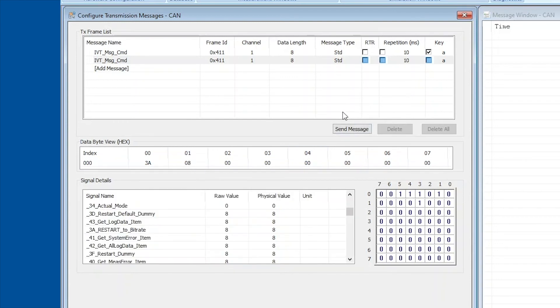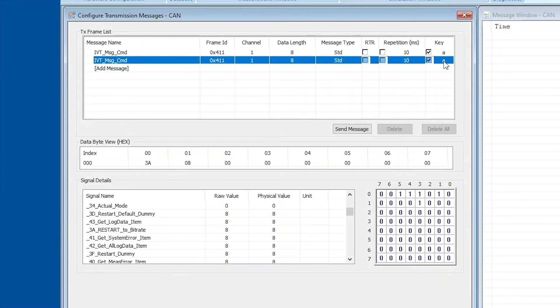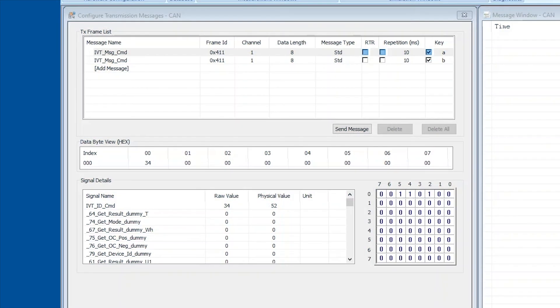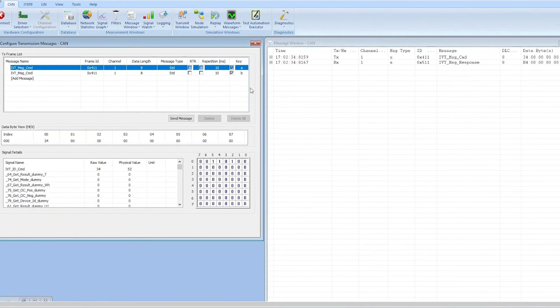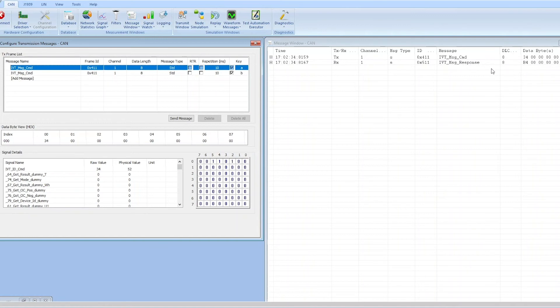Now we're going to assign another key to the second message. We're going to put the check mark and we're going to select the letter B. Now we're ready to send our messages to our IVT-S module. We can simply do that by pressing the assigned keys. Now we're going to go ahead and press the key A on our keyboard, and as you can see in the message window on the right the messages populate in there. You can see the stop message was sent by Busmaster and IVT-S responded with a stop confirmation.